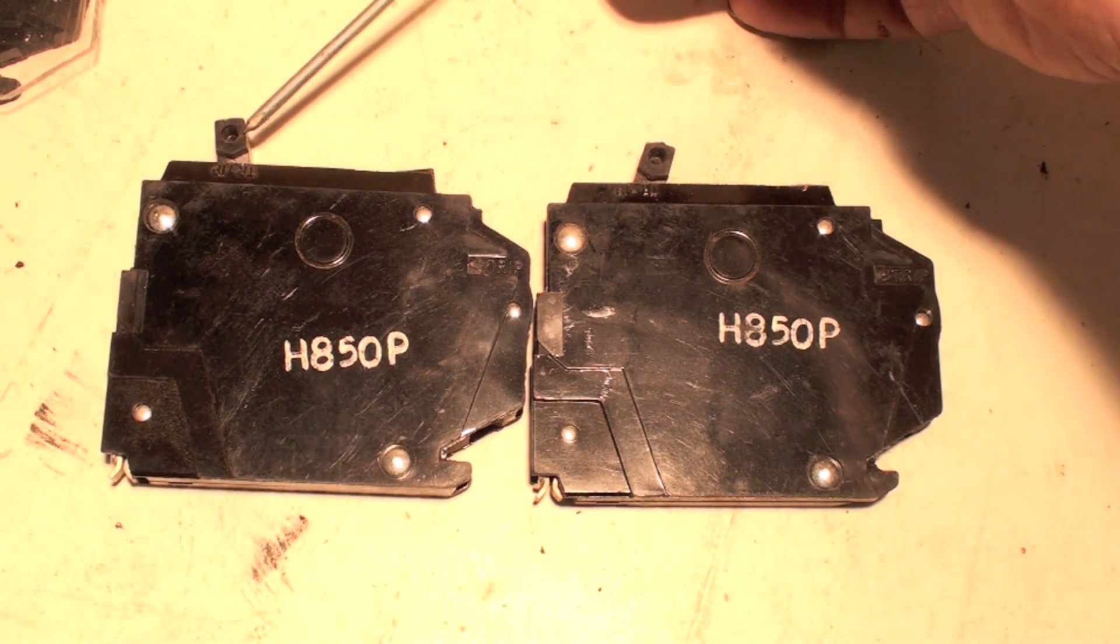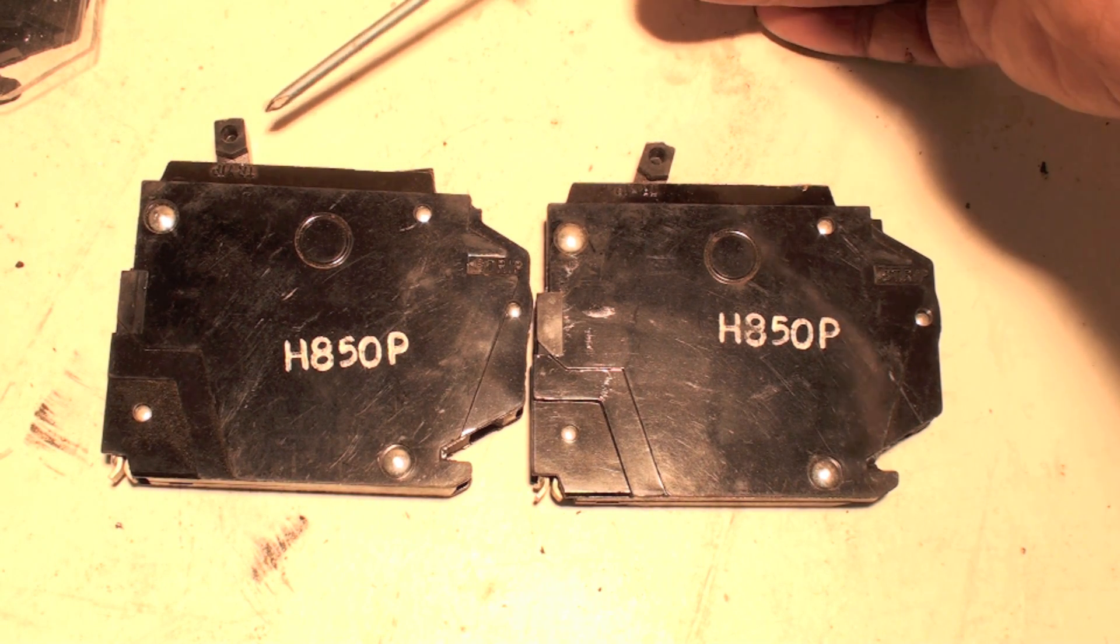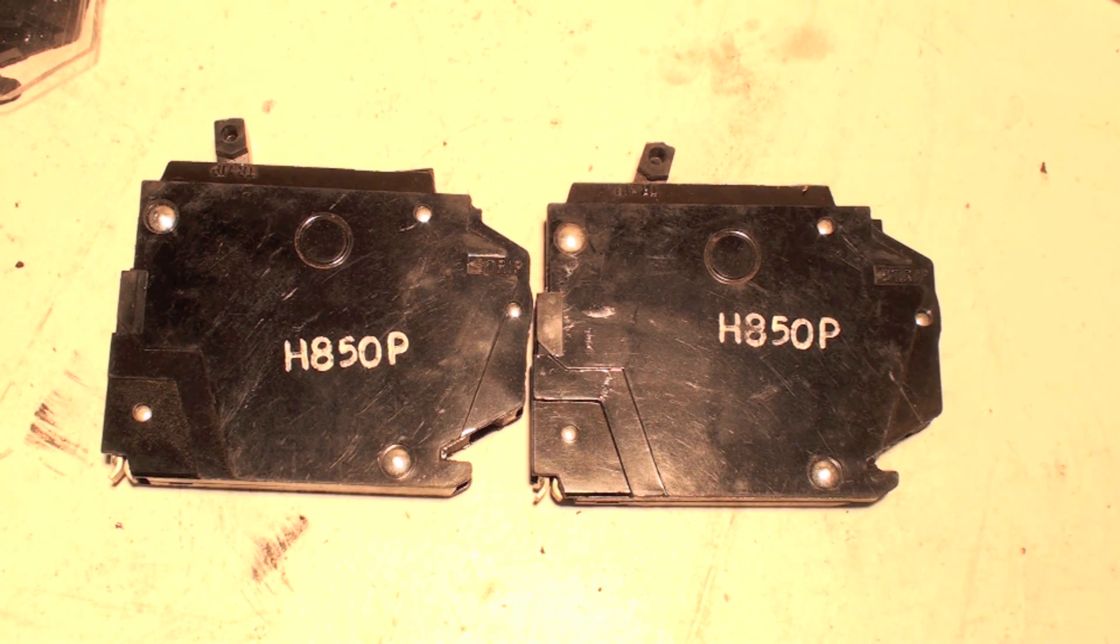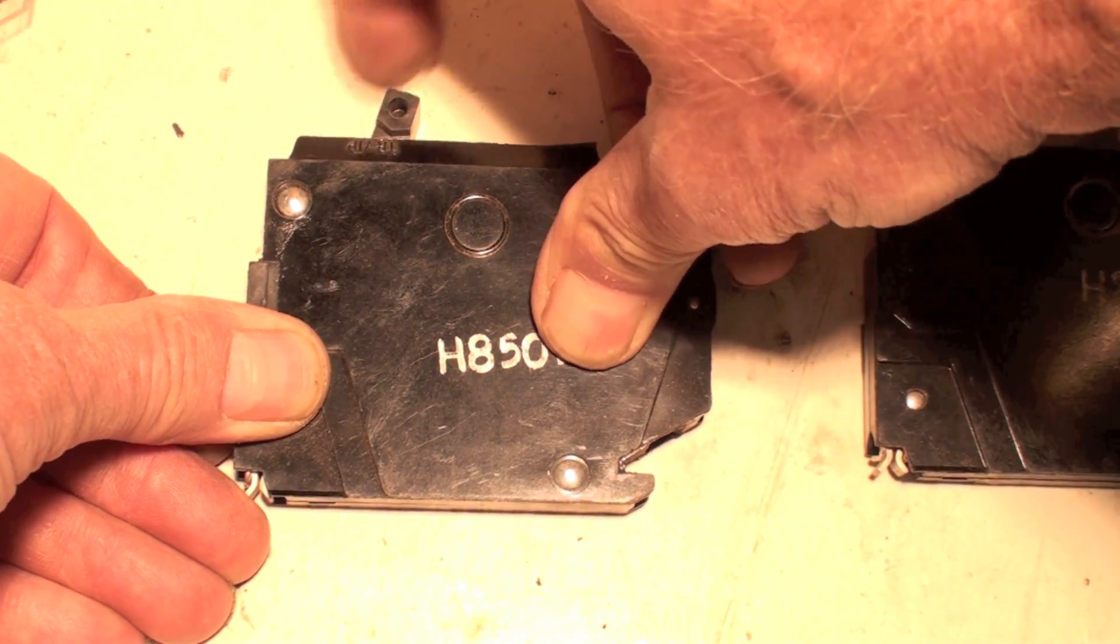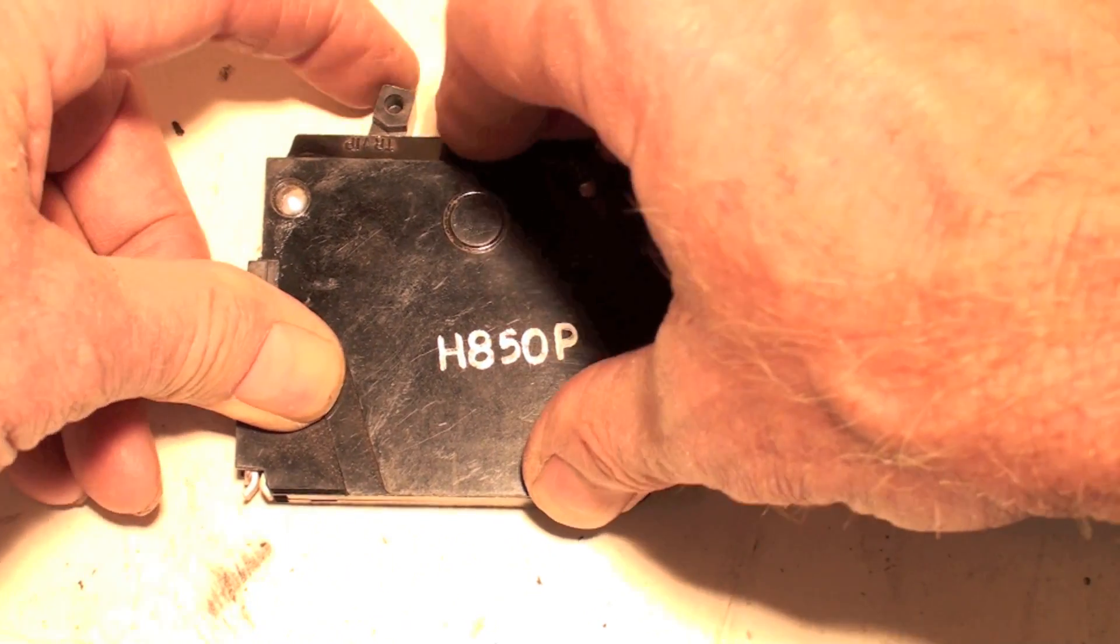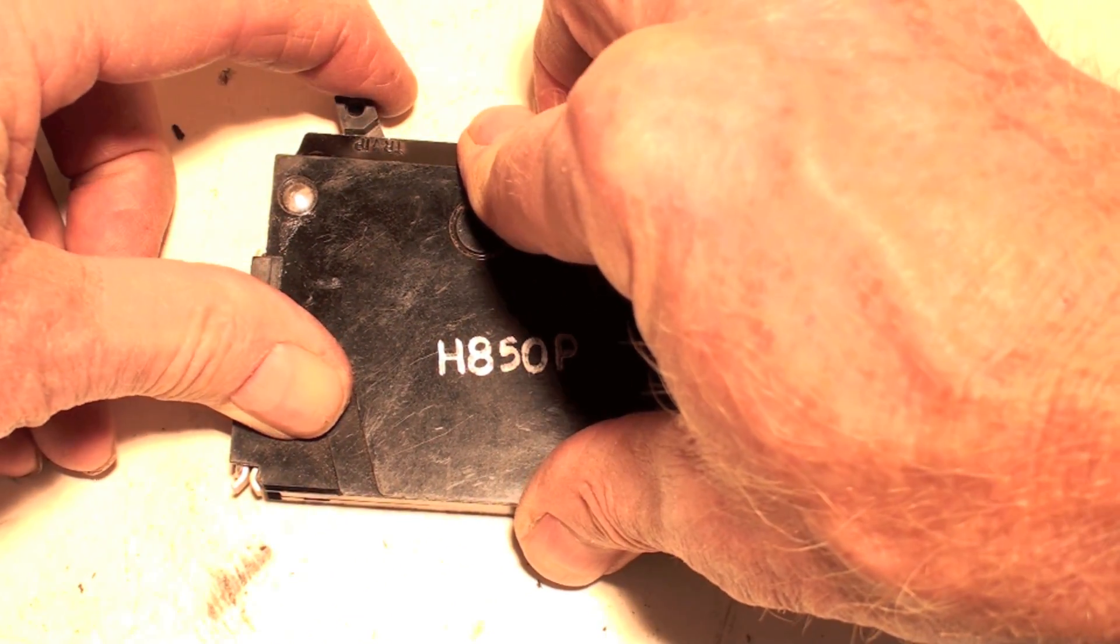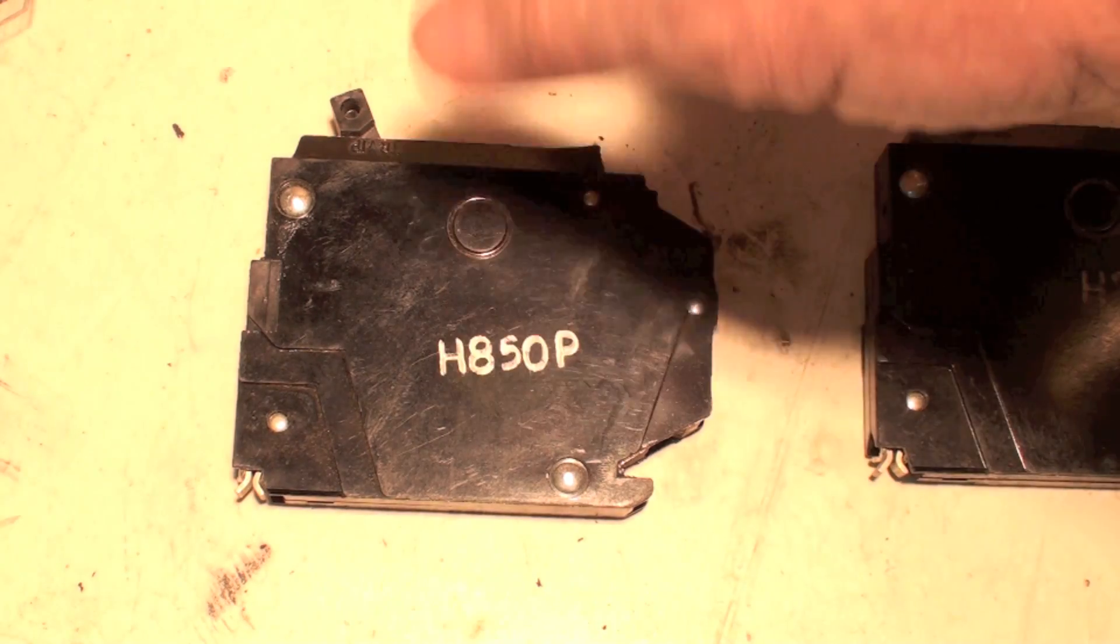Now the only way to get this back on again is, you try to push it to the on position, it won't go. If I pull it all the way over, then if I push hard enough, it'll come back on. So they have to be turned all the way off and back on.